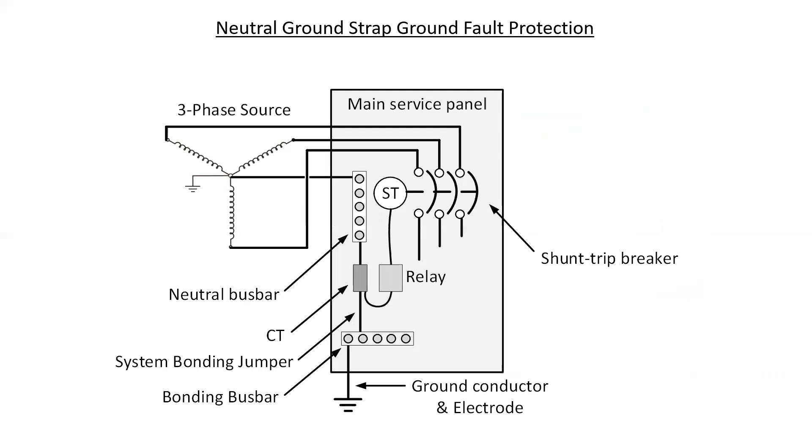This is a neutral ground strap for ground fault protection. What you can see is there is a single CT and that single CT is actually mounted on the system bonding jumper. It then supplies a relay and the relay then connects to the shunt trip mechanism in the breaker. And the relay and the CT and the shunt trip will all be set to a specific current value in order to initiate the automatic tripping or opening of the circuit breaker.